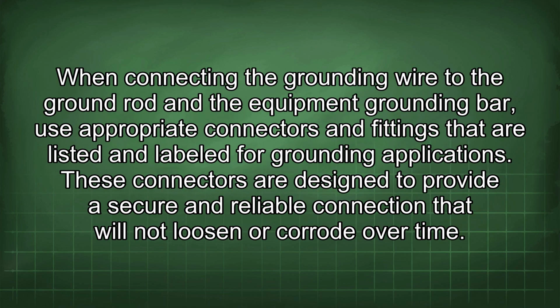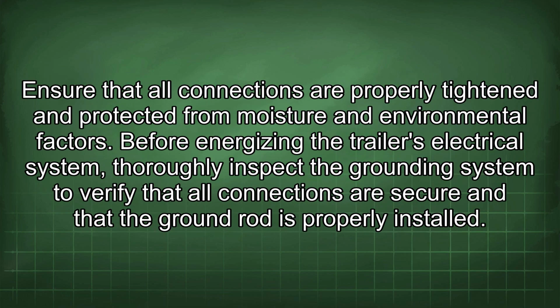When connecting the grounding wire to the ground rod and the equipment grounding bar, use appropriate connectors and fittings that are listed and labeled for grounding applications. These connectors are designed to provide a secure and reliable connection that will not loosen or corrode over time. Ensure that all connections are properly tightened and protected from moisture and environmental factors.